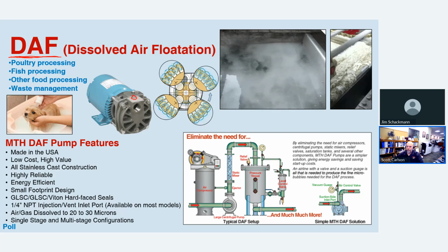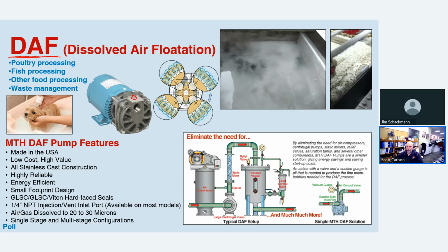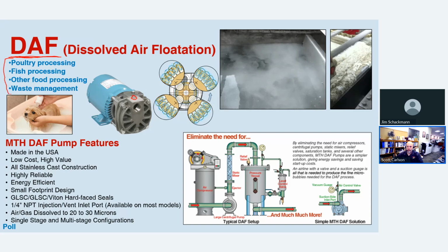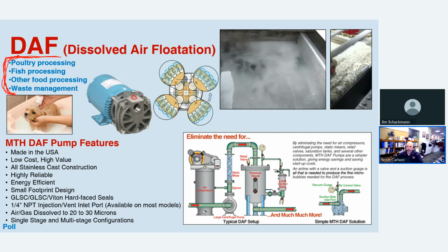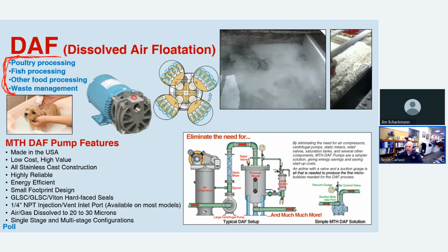When it comes to food processing, a lot of times they filter the water out as much as they can, but they can't put it down the regular drain because of EPA laws and the extreme hardship it would give the wastewater treatment plant. So they use this DAF system. Typically, they used to just store it, and after they get a tanker full of it, they send a truck to come get it and take it to a rendering plant for further rendering. Using a DAF system, they can do it all right there and be able to clean the fluid enough to be able to go right down the drain.